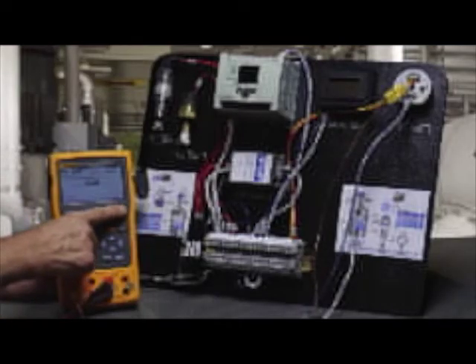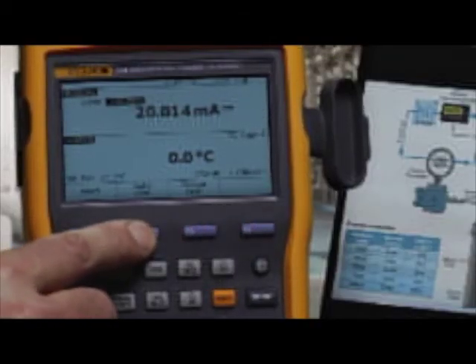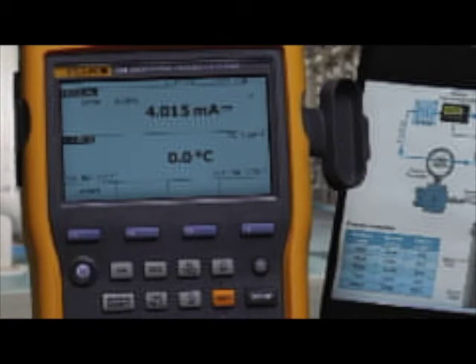After adjustment is complete, we can document the as-left condition of the transmitter after adjustment, and perform the auto test and automatically record the applied temperature, measured current, and error percent of span after adjustment.